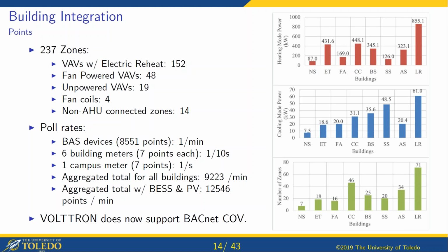The points that we're actually pulling in: we have 237 zones. Of those, 152 have electric reheat on VAVs, another 48 which also do but also have fan-powered VAVs, and then a small assortment of other things. Most of the non-AHU-connected ones have their own cooling loops—they're installed in additions where the air handler doesn't reach.